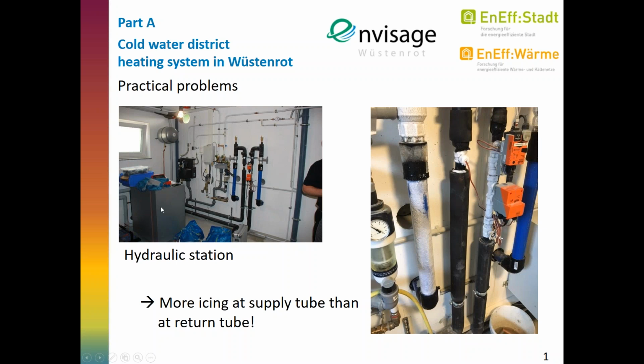We thought maybe the heat pump was connected wrongly to the network — that supply and return had been exchanged — but this was checked by a mechanical person, and everything was correctly connected. Then the service engineer came from the heat pump provider and recognized that they had just put the wrong description on the heat pumps during production: they named supply as return and return as supply. So it was really wrongly labeled, but not wrongly connected — it was due to a wrong description.